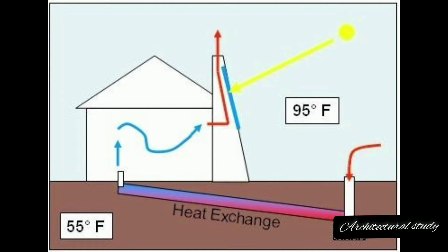Working of the Earth-Air Tunnel — Air Intake: Outdoor air enters through a vent or wind catcher; the depth of the tunnel should be more than 2m, or between 3m and 4m. Underground Heat Exchange: Air flows through the buried pipes, exchanging heat with the surrounding soil. Preconditioning: Pre-cooled or pre-heated air exits the pipes. Building Integration: Air enters the building's ventilation system.